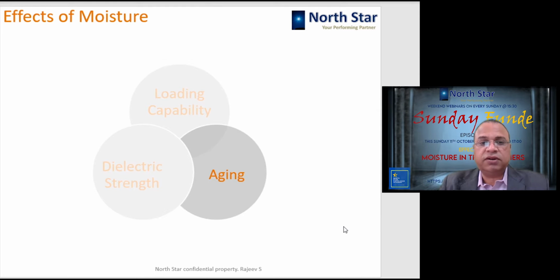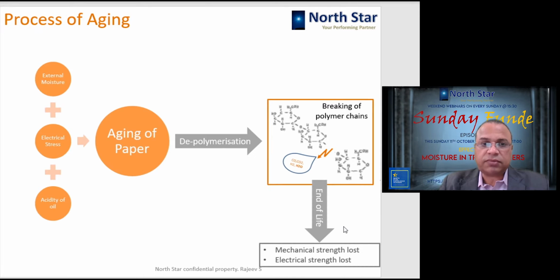Now, what is the effect on aging of the transformer? The most devastating effect of the moisture happens on the life of the transformer. So how does it happen? Aging of the paper happens because of three parameters. One is the external moisture, second is electrical stress, the insulation is subjected to electrical stress, and then the acidity of the oil. So these three factors cause the aging of the paper.